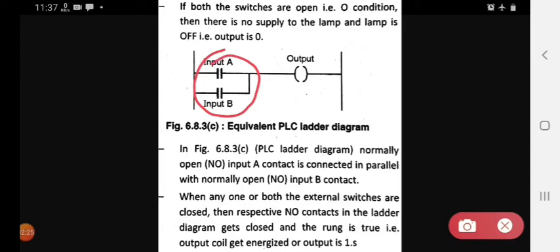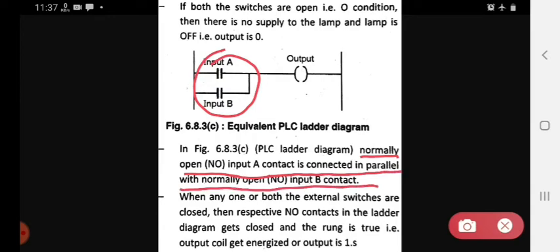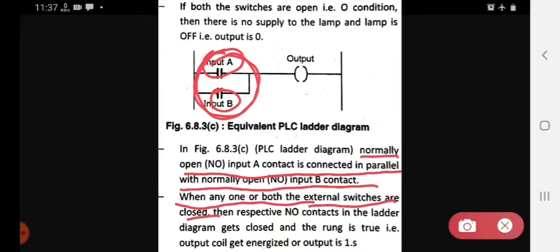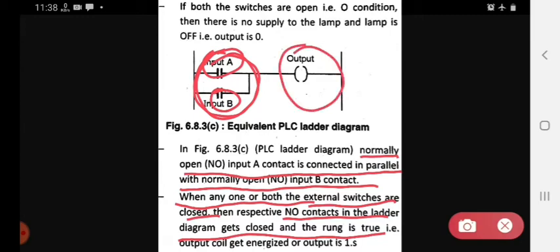Then we see the ladder diagram of OR function. In this ladder diagram, the two normally open contacts are connected in parallel. Normally open input A contact is connected in parallel with the normally open input B contact. When any one or both external switches are closed, the respective normally open contacts in the ladder diagram get closed, the condition is true, and the output coil gets energized.